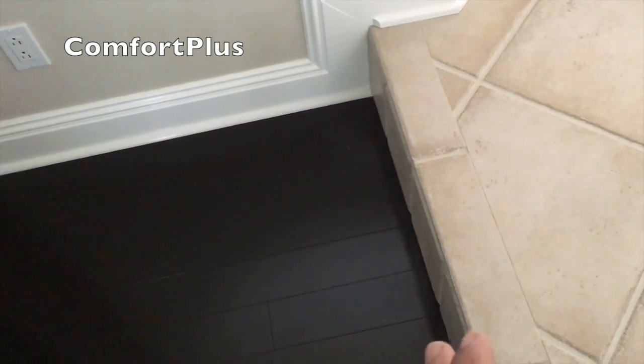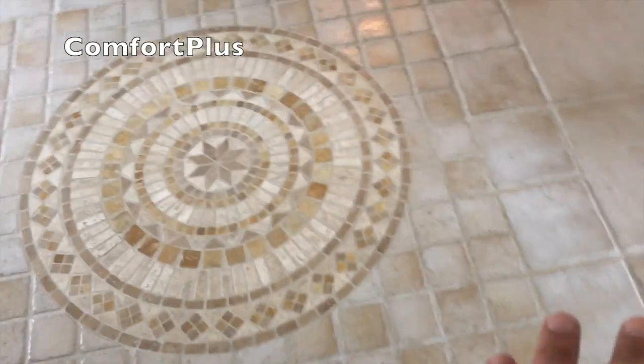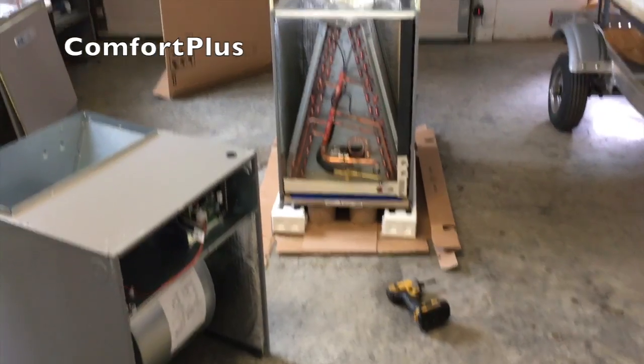So the ductwork on this level is up against the bottom of the floor joist, as is the ductwork down here, but I have to get beneath this steel beam somehow to get to this other zone. So what I'm going to do is fabricate a piece of trunk duct with 2 8x20 ducts going each direction with zone dampers. Okay, here's the air handler.